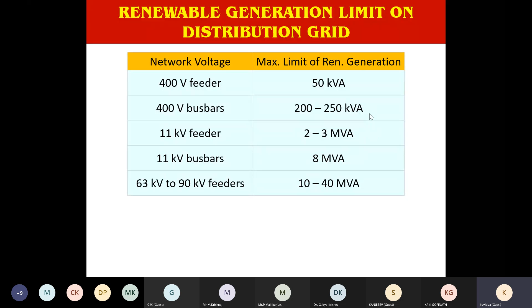See, there is a requirement that the higher the voltage where you are connecting these resources, the safer it will be. And in our country, of course, there is a notification from, I think, CERC, Jawaharlal Nehru National Solar Mission, that 5 megawatt and above systems must be connected to a minimum of 33 kV. Because if it is lesser than that, then if a PV system fails, the entire system will be affected. But if it is connected to a higher system, like in a thermal power plant, suppose there is a 2000 megawatt station in which you have a 10 megawatt PV, that is nothing. It will not create any problem. But if a 10 megawatt system is connected to, say, a 20 megawatt system, then the impact will be severe.